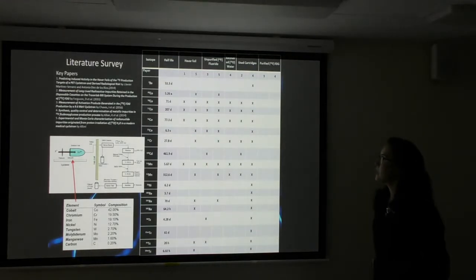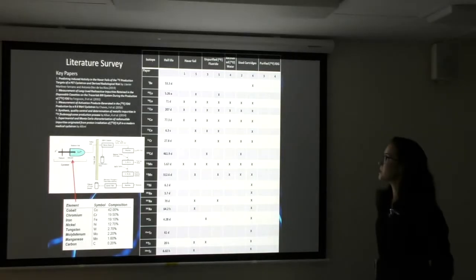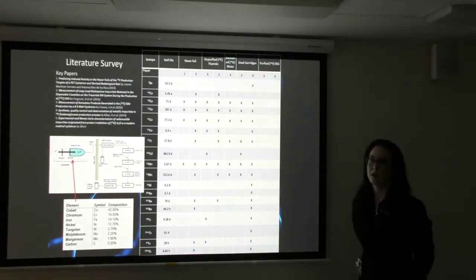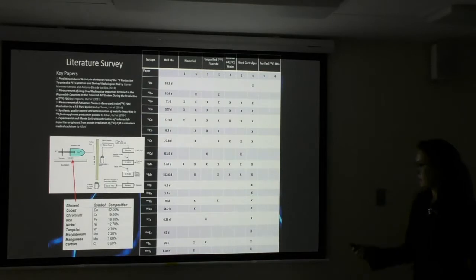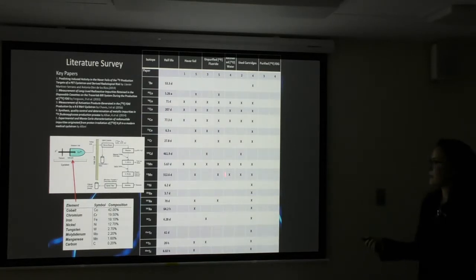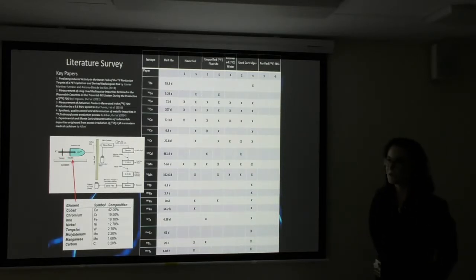As you can see, they mainly picked up cobalt contaminants, which is expected because Havar is mainly a cobalt alloy. I will also point out that 2 papers found cadmium-109. The only reason why they found this is because they used a silver window here, whereas we use titanium, so I'm not expecting to find this one in any of my results.